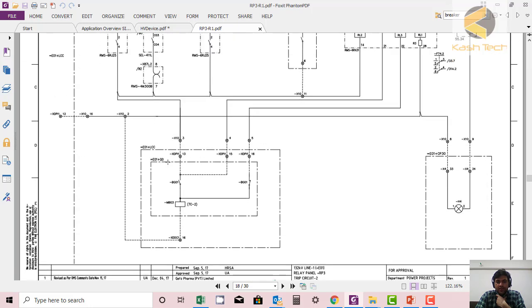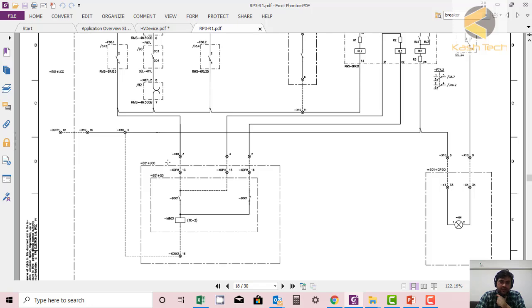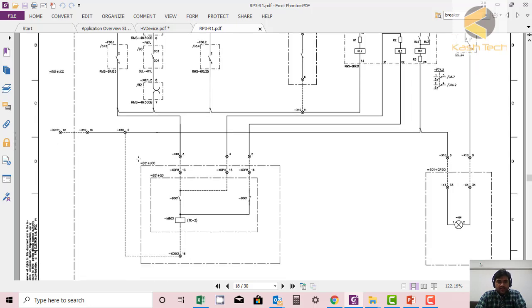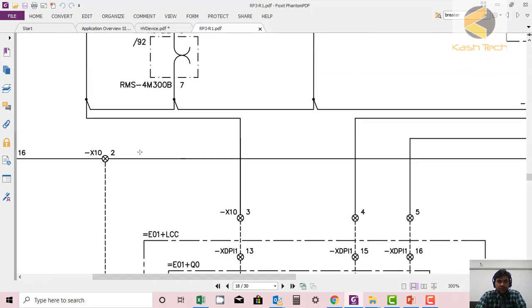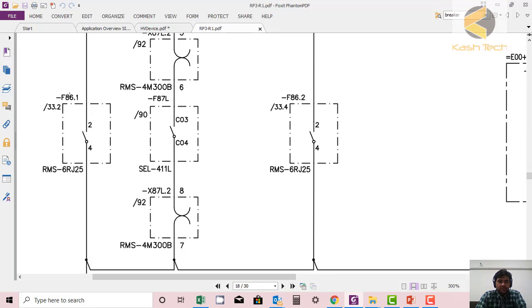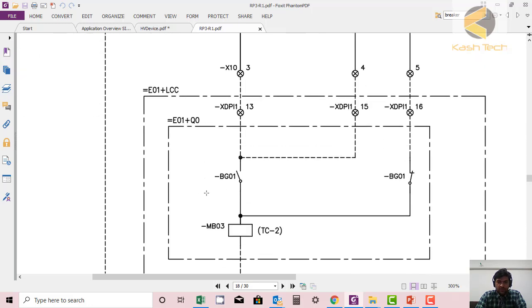There are two trip coils in the circuit breaker. That was TC1, trip coil one. Now this is trip coil two. You can see again that lockout relay F86.1 will operate through the differential relay, then make tripping through the auxiliary contact, and this tripping coil two will be energized and trip the breaker. I hope you enjoyed the lecture — let's move to the next lecture. Thank you.